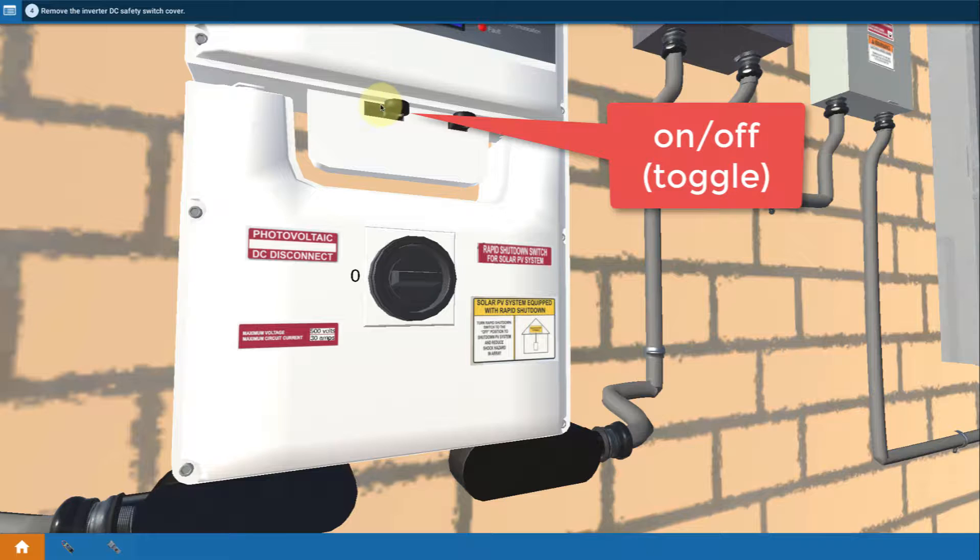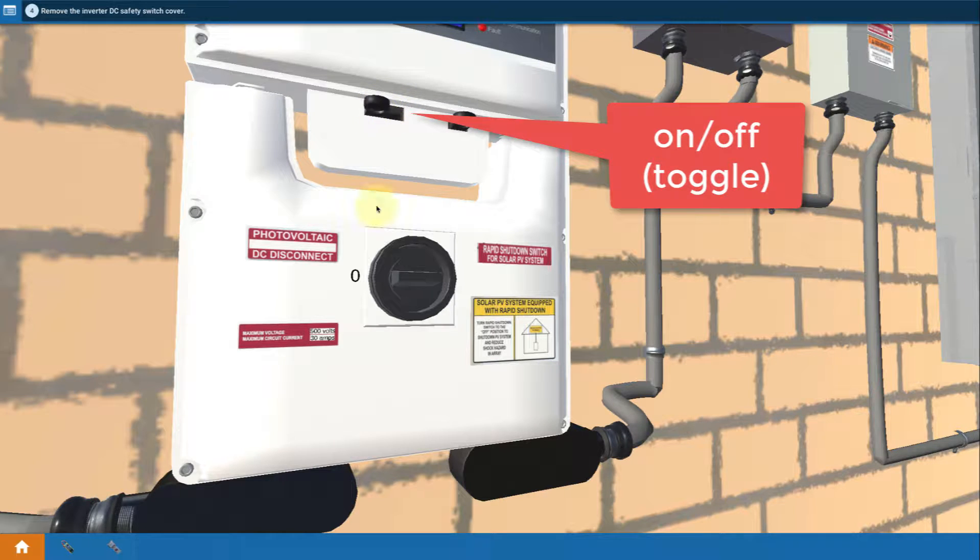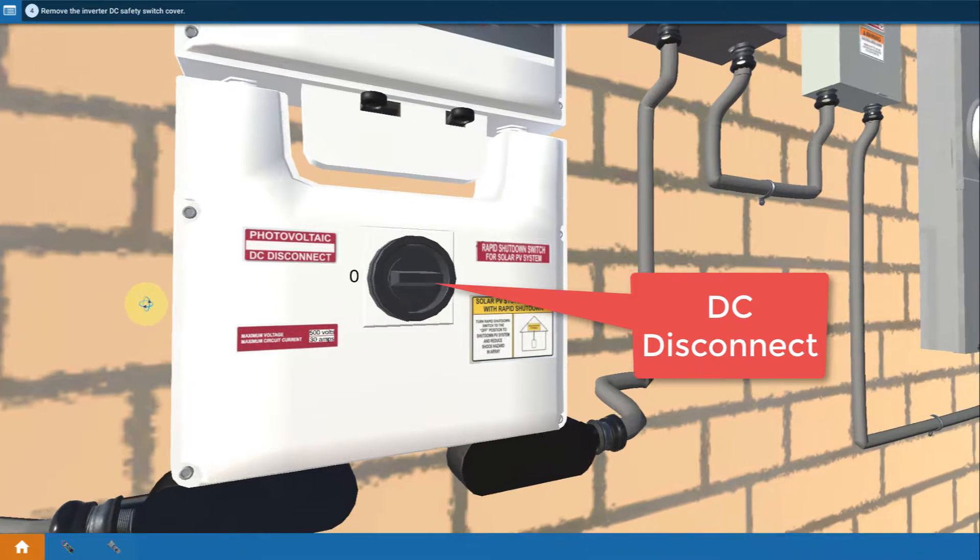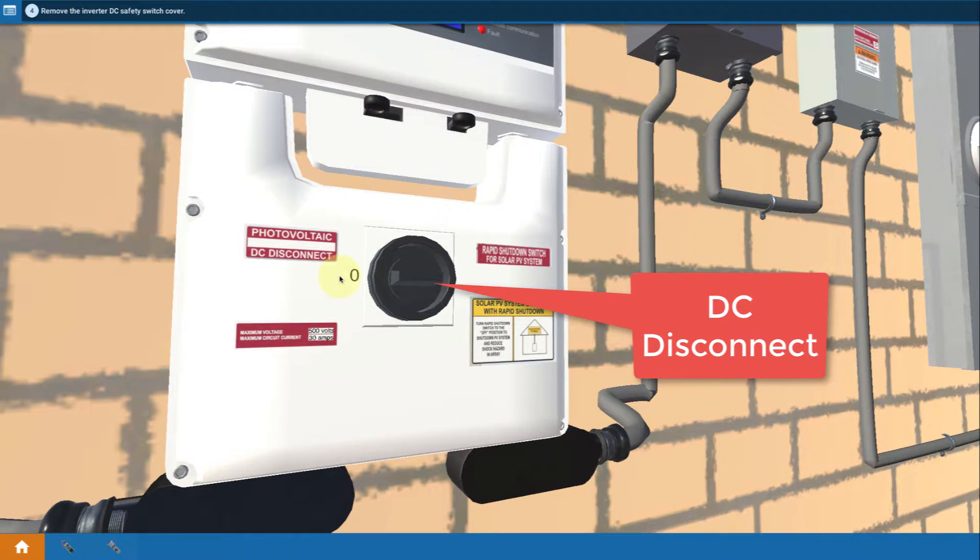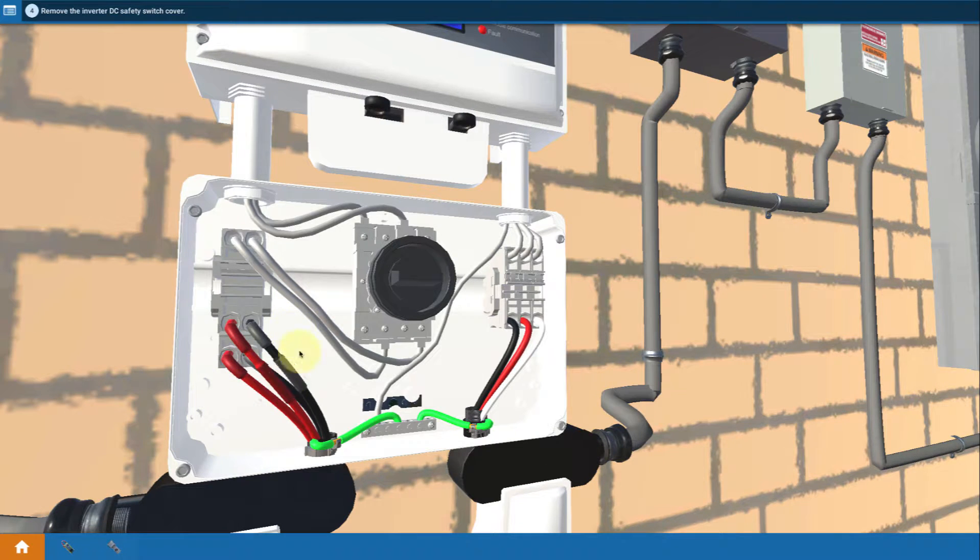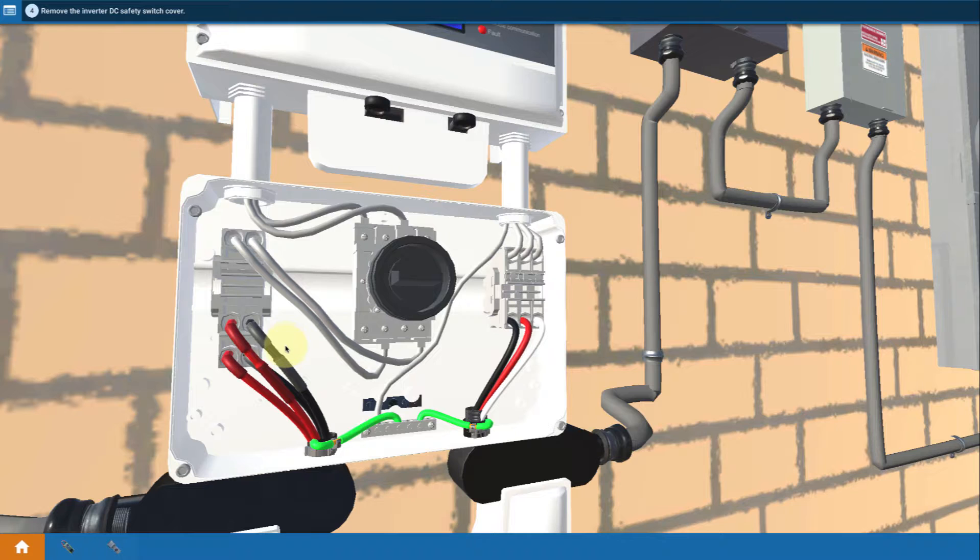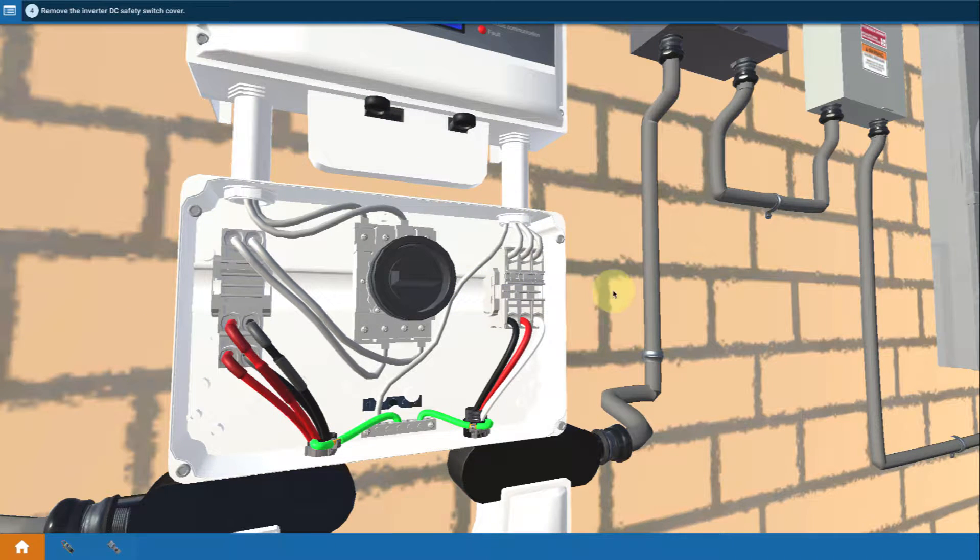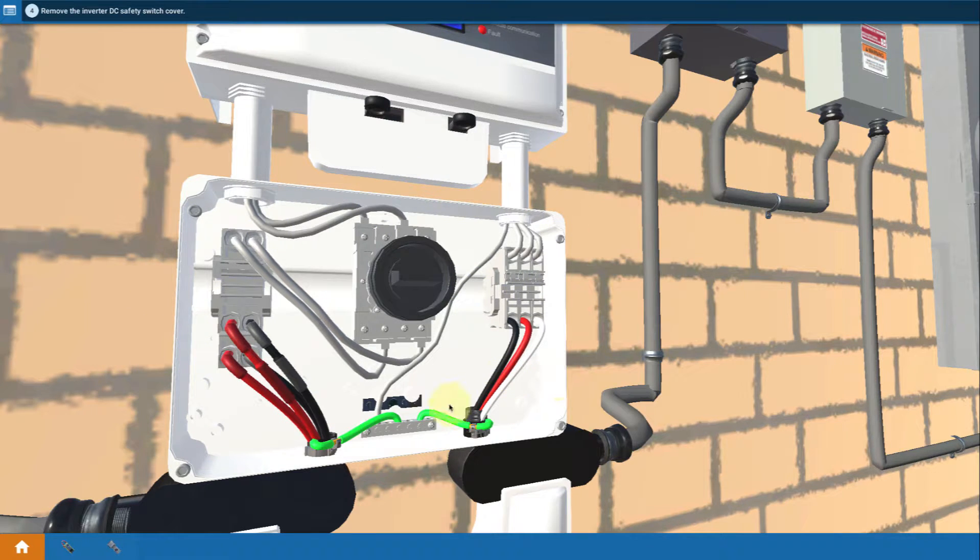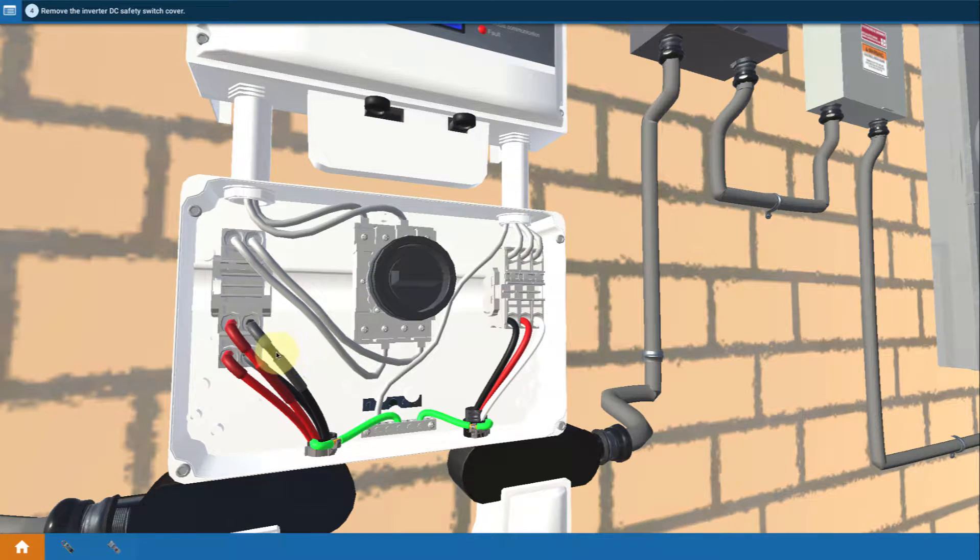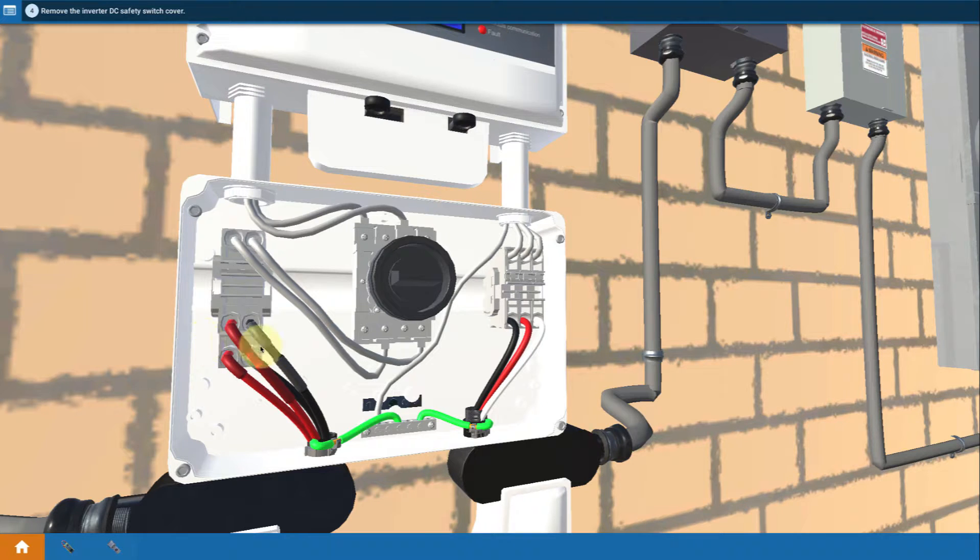There's this upper switch, which is often called an on-off switch, and then there's this main power switch down here on the DC disconnect. So this big switch is the one that actually controls the connection of the inverter to the array, right here. And you're going to wire up these things. So this is the main DC power disconnect. It's the DC safety switch. And this whole area is the DC safety switch enclosure. This switch turns off any connections coming in from the array to the inverter. So you turn this off, it's got no connection to the array whatsoever.